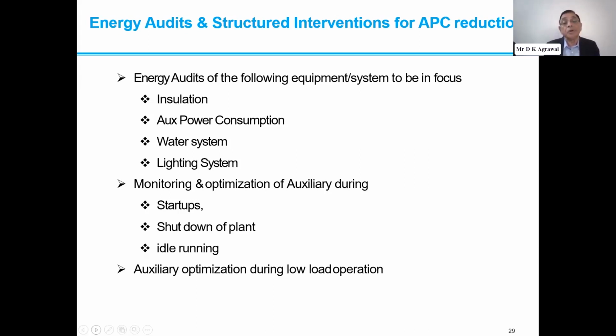And similarly, monitoring and optimization for startup and shutdown. There are some utilities where I have seen they have prepared a chart: for a startup, what are the auxiliaries which will be needed; when you have come to the synchronized position, what are the auxiliaries which will be in service; and when you are going beyond a certain load, what other auxiliaries will be brought in? There should be a set procedure, so that whichever shift the unit is coming in, everybody is aware that this is the system, this is the procedure, and these are the auxiliaries to be running in startup and during synchronization.